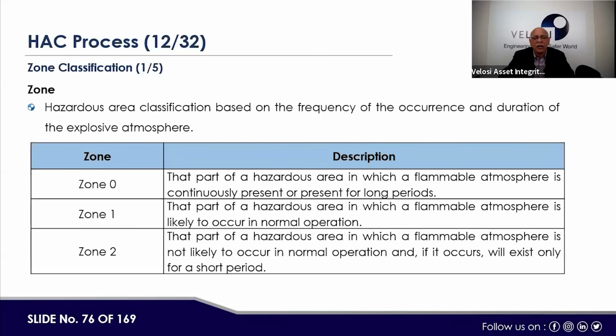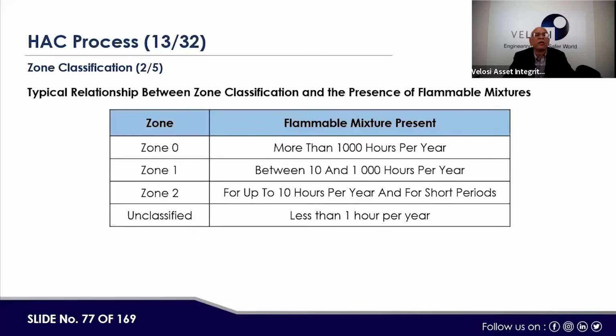We already touched on it: zone 0, zone 1, zone 2 as per IP-15, also keeping API 505 in mind. Then zone 0, zone 1, zone 2, and unclassified. The typical relationship between zone classifications, in terms of time, is more than 1,000 hours, 10 to 1,000 hours, and less than 10 hours, or unclassified areas, where a hydrocarbon release could take place for less than 1 hour per year.